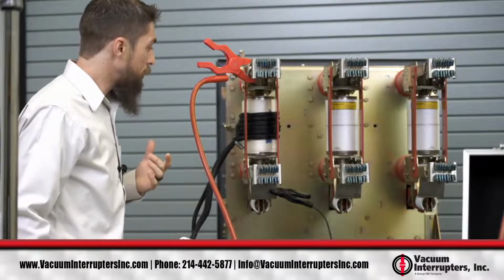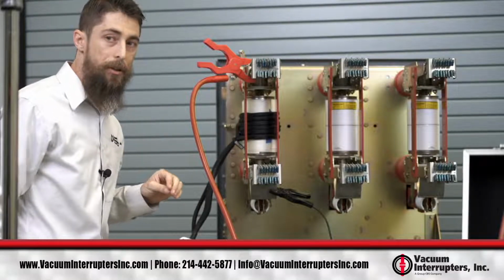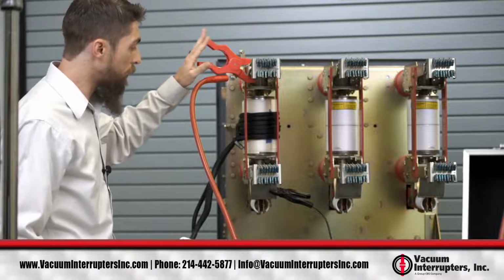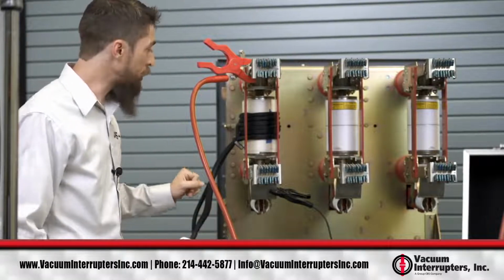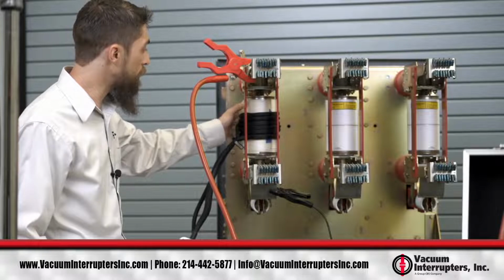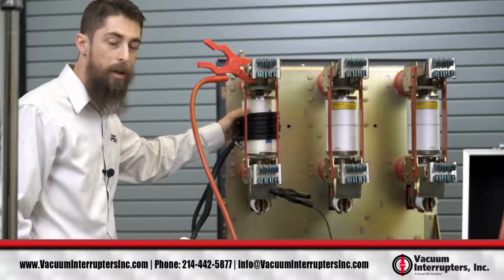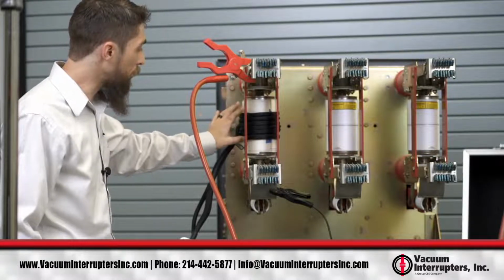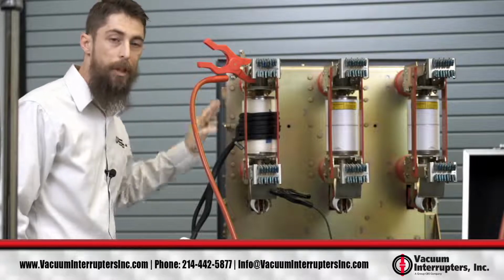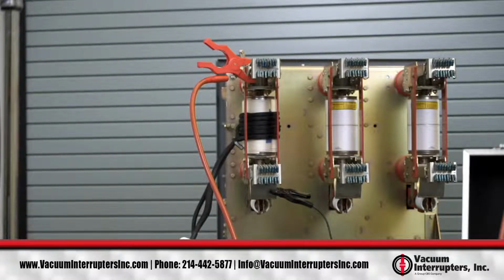And just the best practice is to put your high voltage on top and your signal on bottom, just in case there is an accidental movement of the coil and it were to fall down. You don't want the coil to fall down while the high voltage is being applied. So now I'm going to run the test.